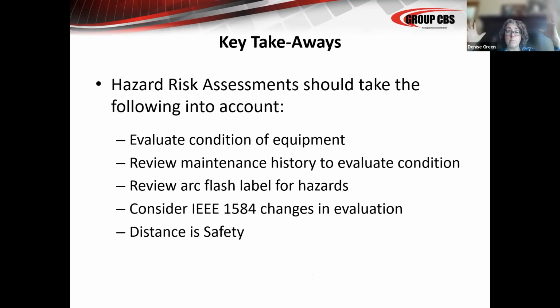And then my last slide is sort of the takeaways. When you're doing your hazard risk assessments, evaluate the condition of your equipment and the maintenance history to see, has this equipment really been maintained? If you're only maintaining stuff every 8 to 10 years, know that your lubricants are not going to work like they were designed to do in the 3 to 5 years that the manufacturer of both the switchgear and the lubricant recommended.